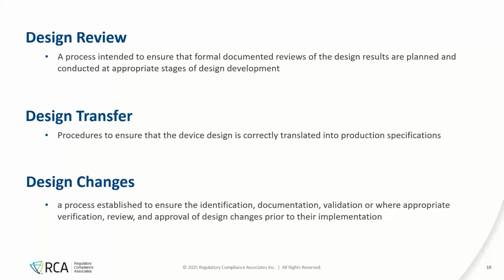Design transfer. So once you have the design verified, typically as you're going into verification or as you've finished the first part of verification testing, you need to start your design transfer. This is a documented and outlined procedure where you transfer the design from R&D to manufacturing. So you're establishing all those design outputs that you took and you're making them manufacturing processes. You have a master validation plan for your manufacturing processes. Think about the fill line, the pack line, sealing machines, things like that. Setting all that up, determining all the right settings for those things, doing procedural or process risk assessments, things like that. This all happens in design transfer.